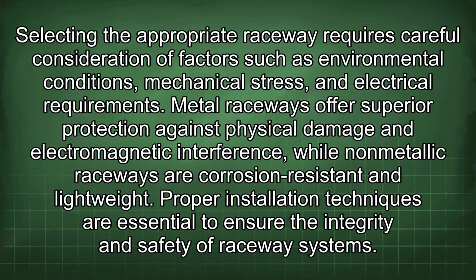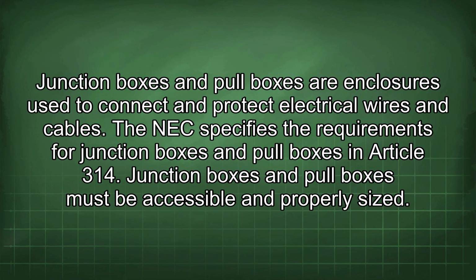Selecting the appropriate raceway requires careful consideration of factors such as environmental conditions, mechanical stress, and electrical requirements. Metal raceways offer superior protection against physical damage and electromagnetic interference, while non-metallic raceways are corrosion-resistant and lightweight. Proper installation techniques are essential to ensure the integrity and safety of raceway systems. Junction boxes and pull boxes are enclosures used to connect and protect electrical wires and cables. The NEC specifies the requirements for junction boxes and pull boxes in Article 314. Junction boxes and pull boxes must be accessible and properly sized.